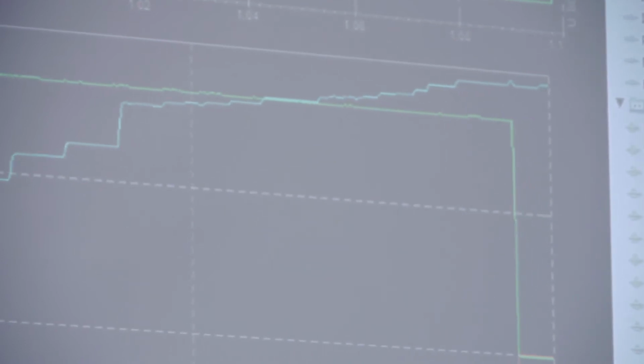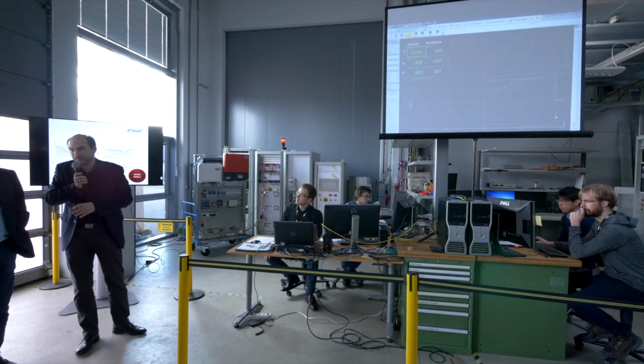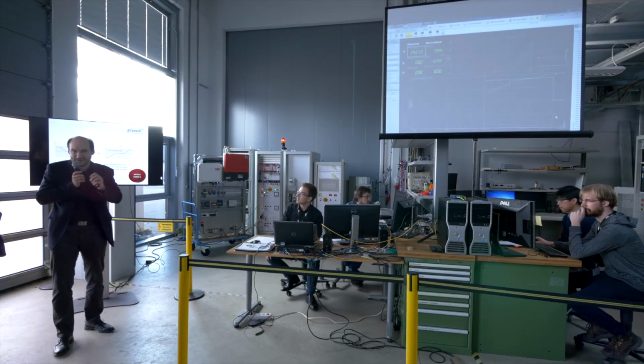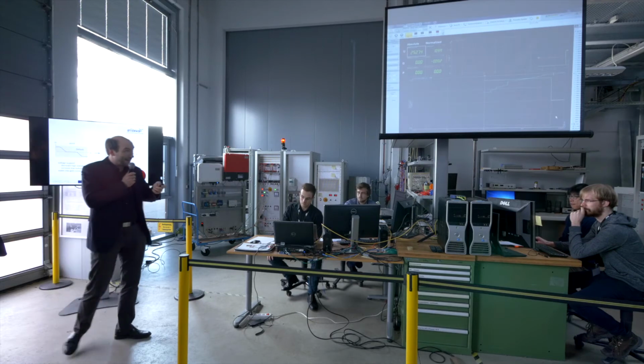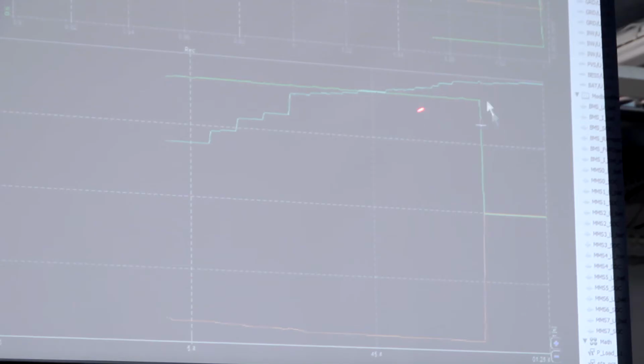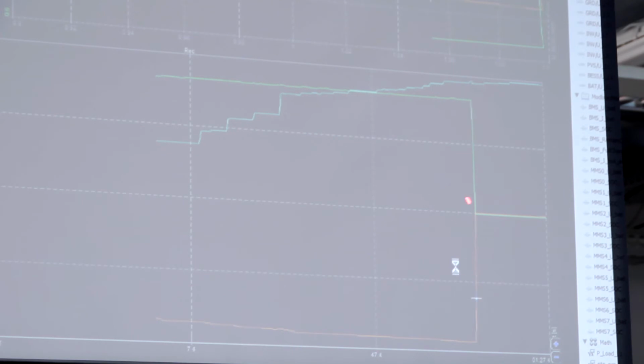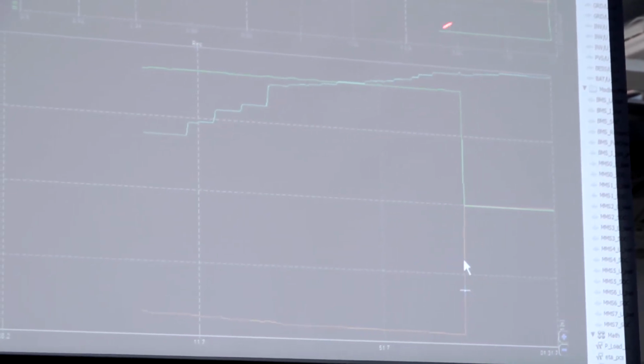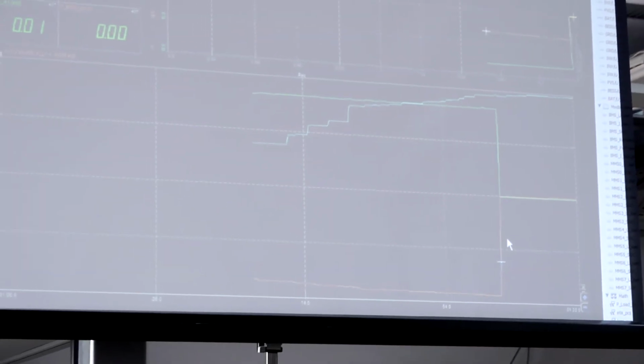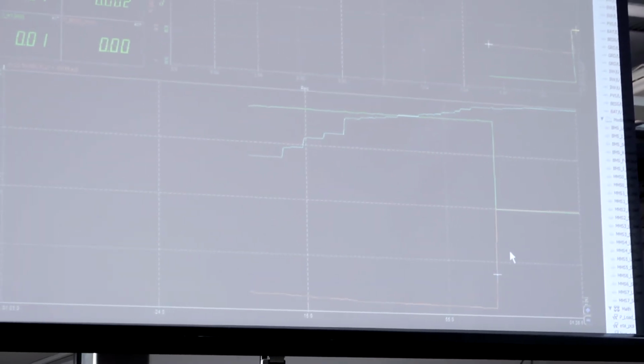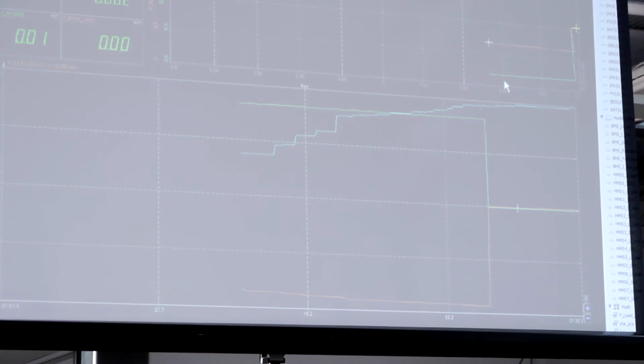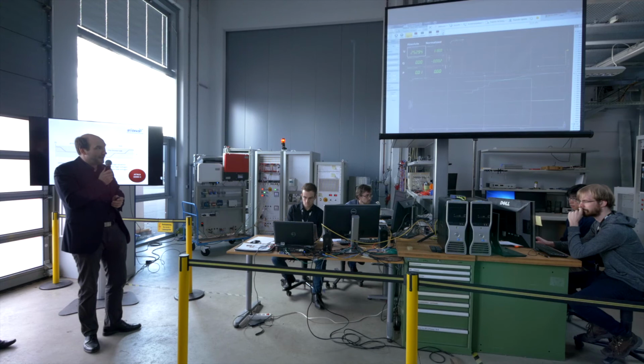And there we are, so this time it worked. What happened here is the inverter has a protection mechanism: when the voltage gets too high, it will disconnect from the grid, and that's what happened here. You see the reactive and active power went to zero, so there's a disconnection from the grid. This doesn't have much effect on the voltage here because this is just one - all the other systems are still running, but this one has disconnected, and the others in the simulation will do so later.